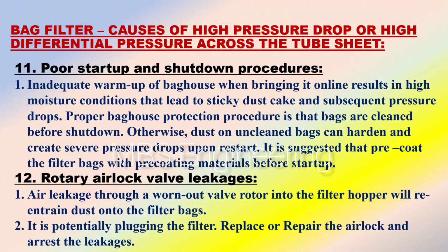One of the main causes of high differential pressure is the baghouse system's poor startup and shutdown procedures. Point number 1. Inadequate warm-up of the baghouse when bringing it online results in high moisture conditions that lead to sticky dust cake and subsequent pressure drops. Point number 2. Proper baghouse protection procedure is that bags are cleaned before shutdown. Otherwise, dust on uncleaned bags can harden and create severe pressure drops upon restart. It is suggested to pre-coat the filter bags with pre-coating materials before startup.